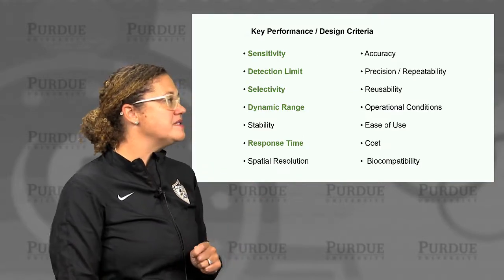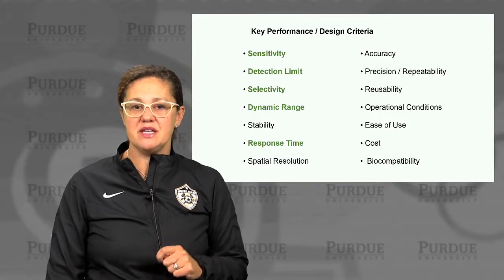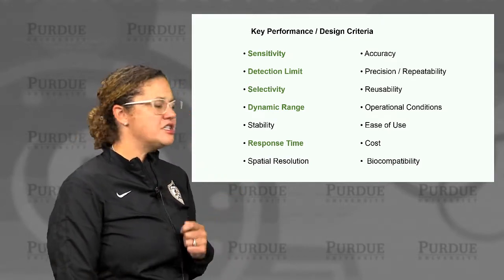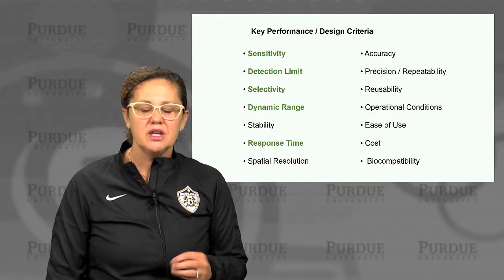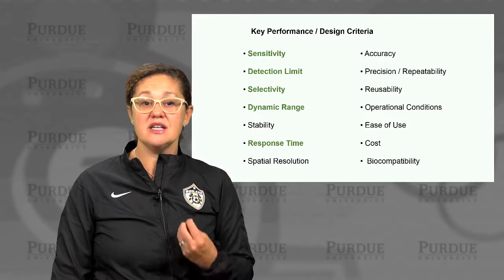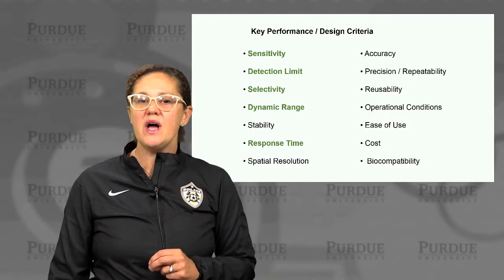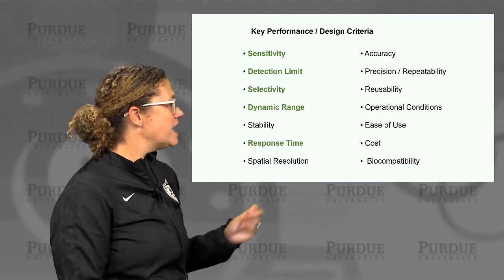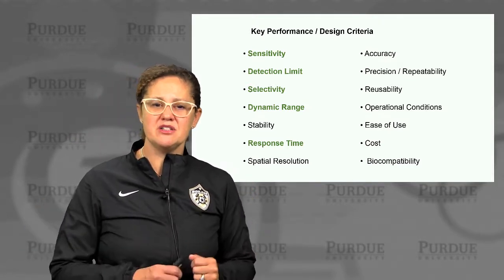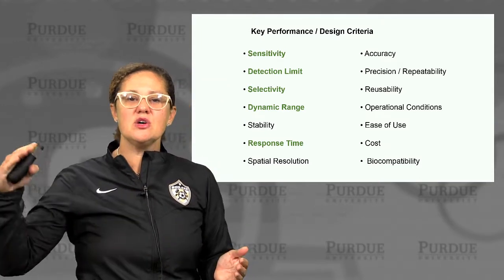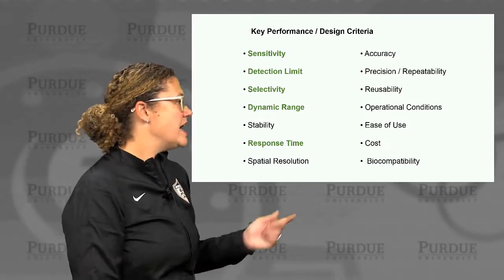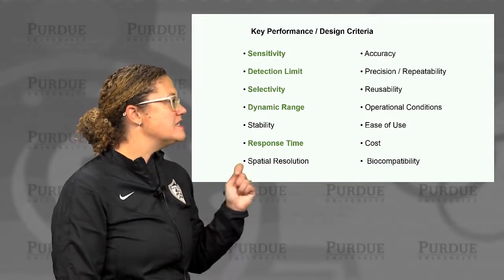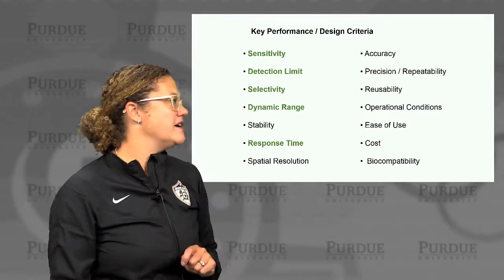There are several key performance or design criteria of a biosensor. We can talk about its sensitivity, which we'll go into in more depth in an upcoming lecture. We can talk about the detection limit — essentially how few of the entities need to be present before our sensor can detect them. Selectivity: how well our sensor can detect one component versus some other similar component. Dynamic range spans from our detection limit up to where we can no longer distinguish differences. And response time: how quickly do we get a signal out of our system. These five are really the key driving performance criteria of most sensors.